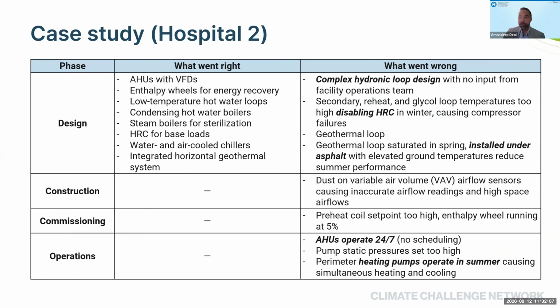What went right was exactly what was in the previous hospital: the design included all the elements that you would expect to see. However, what went wrong was the complex design as a starting point. The hydronic loop was made so complex that neither building operations team was able to understand how it was fully utilized. As a result, the key component where energy use would have been reduced, the heat recovery chiller, got disabled, because the knowledge from the design team did not get passed on to the operations team in a way that they completely understood how the system was designed, what the original intent of the design was, and how that translates to operations.